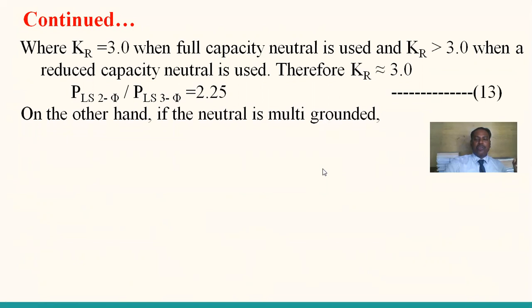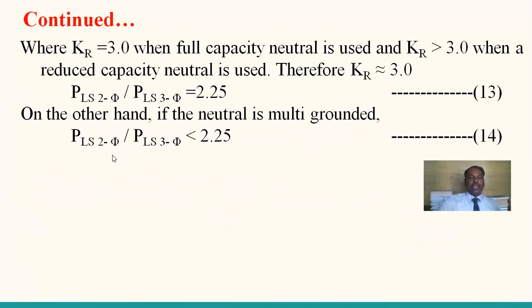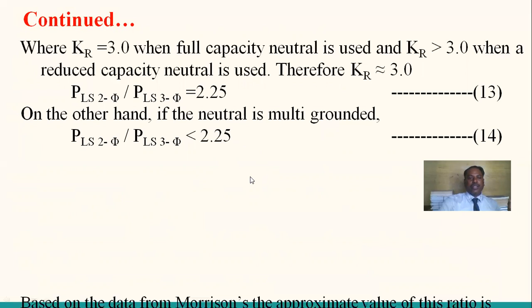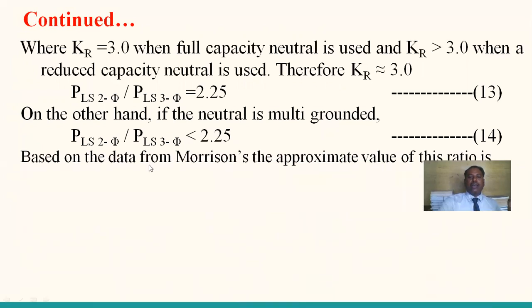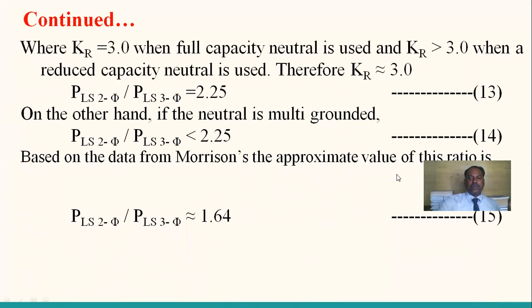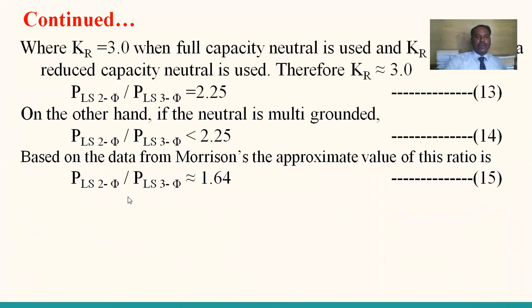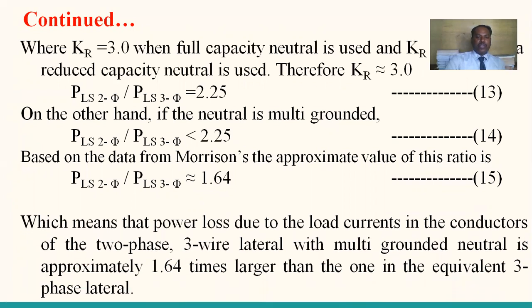On the other hand, if the neutral is multi-grounded, according to Morrison, the value of PLS two-phase by PLS three-phase is less than 2.25. It is for multi-grounding. Based upon the data from Morrison, the approximate value of this ratio, PLS two-phase by PLS three-phase, is approximately equal to 1.6. This is equation number 15, which means that power loss due to the load currents in the conductors of the two-phase three-wire lateral with multi-grounded neutral is approximately 1.64 times larger than in the equivalent three-phase lateral.